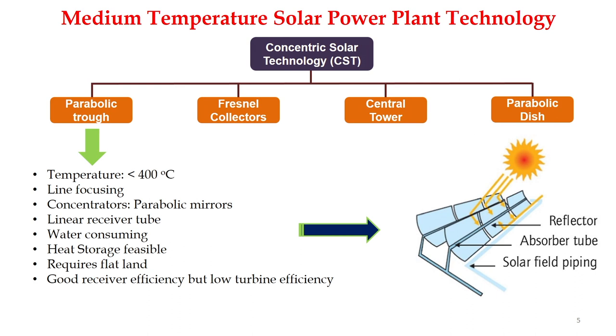Parabolic trough: its temperature range is below 400°C and it is a line focusing system, meaning only single axis tracking is employed. These concentrators are parabolic mirrors and it has a linear receiver tube. This system consumes water and heat storage is possible — once hot fluid is generated, it can be stored in an insulated vessel to exchange heat with water and generate steam to produce electricity. The system requires flat surfaces and has good receiver efficiency but low turbine efficiency.